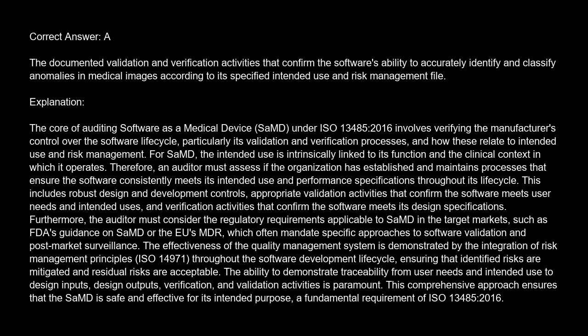The correct answer is A, the documented validation and verification activities that confirm the software's ability to accurately identify and classify anomalies in medical images according to its specified intended use and risk management file. Explanation: the core of auditing software as a medical device, SaMD, under ISO 13485:2016 involves verifying the manufacturer's control over the software lifecycle, particularly its validation and verification processes, and how these relate to intended use and risk management.